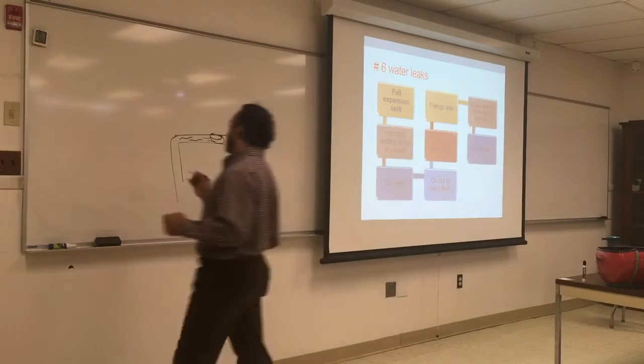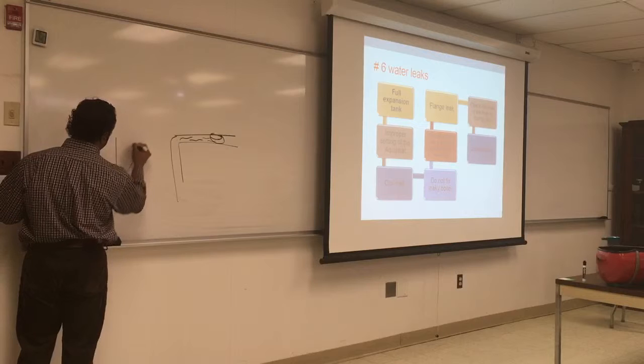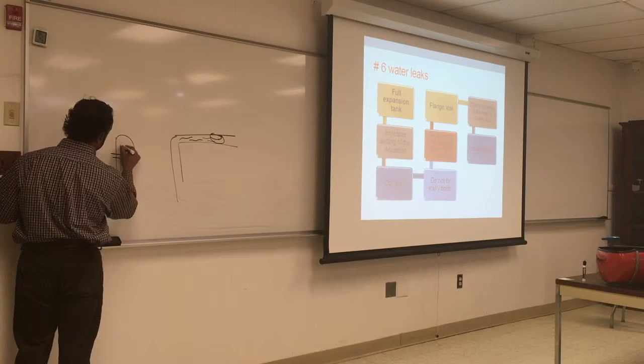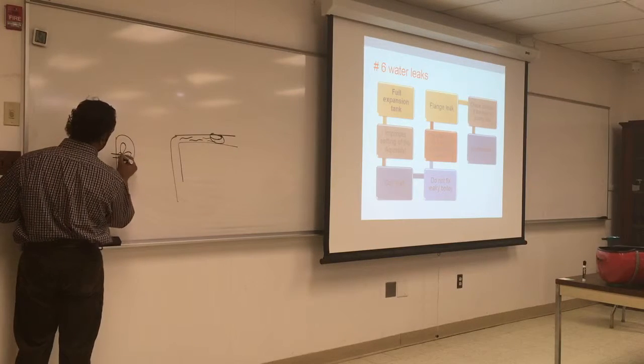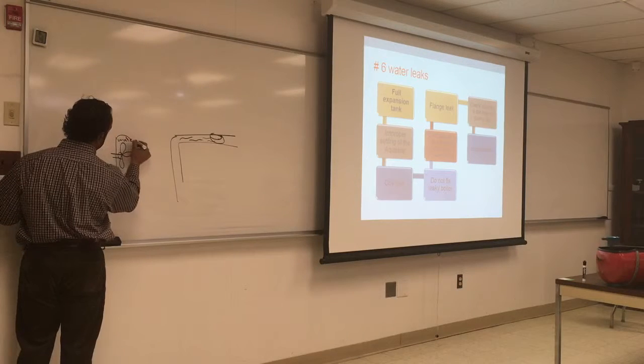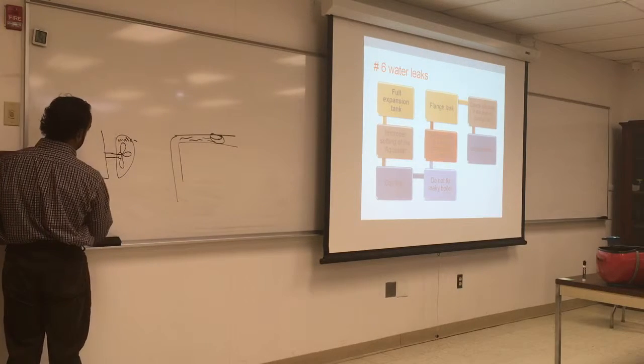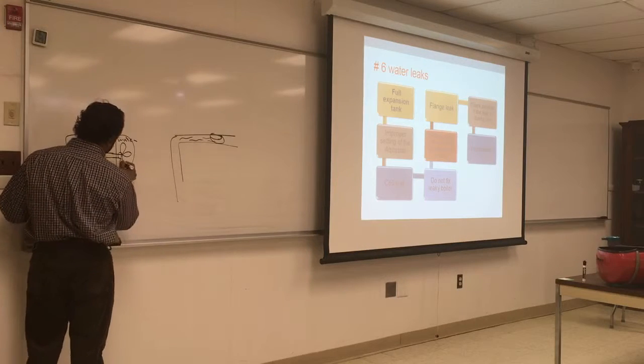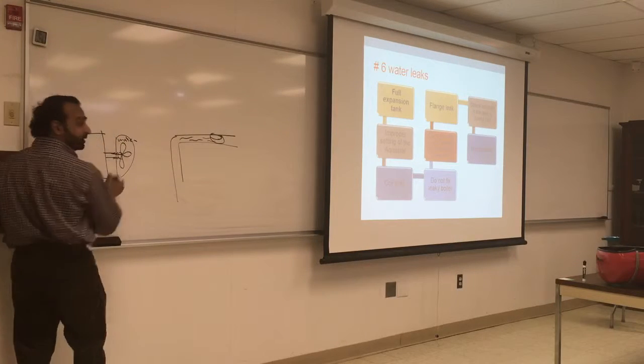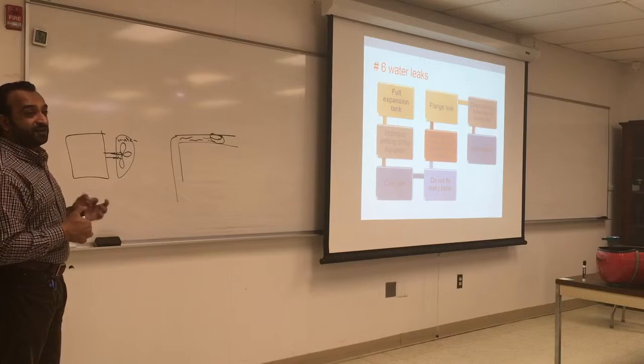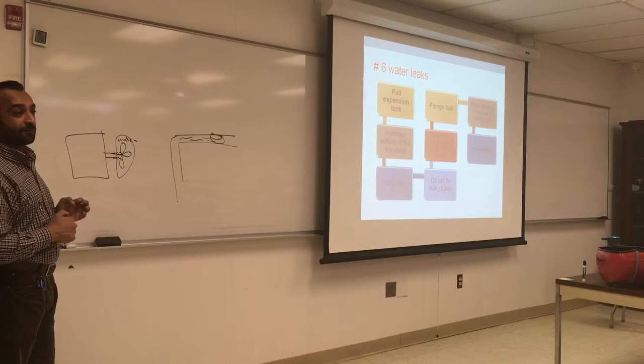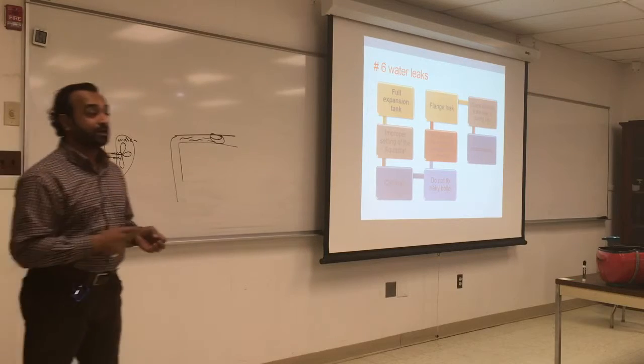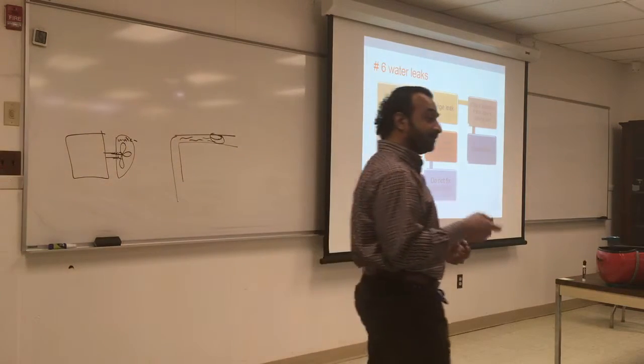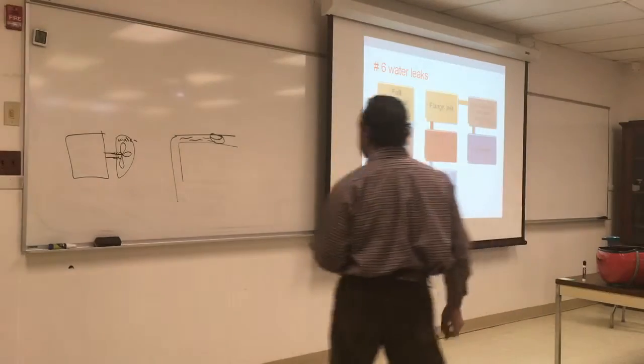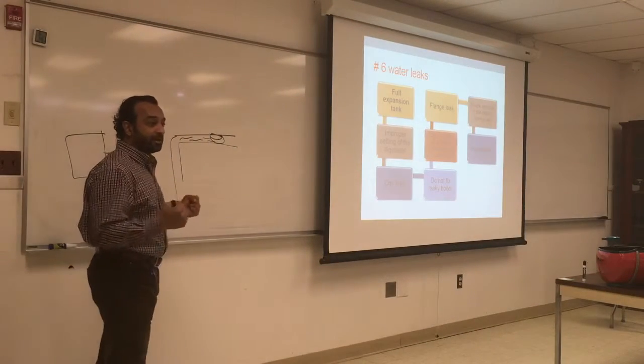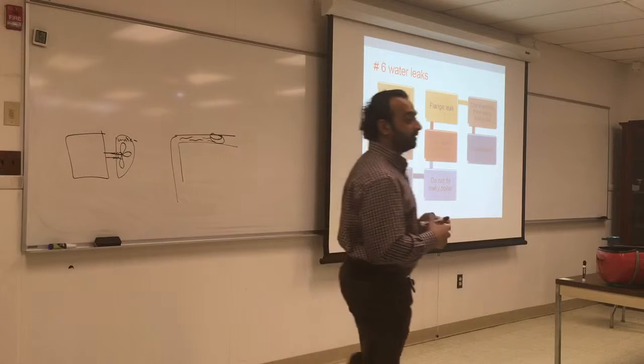into the motor. So if you look at the pump on the inside, this is the shaft. This is the impeller. There's water in here. This is the motor. So how come the water is not coming out from this little opening? It's very, very small and sized correctly, like to the micron, so it will not move. Over time with spinning, it might leak. And usually they put a lot of flanges and bushing in here. They'll provide some kind of cushion for the water not to leak.